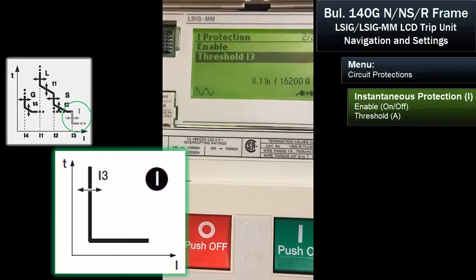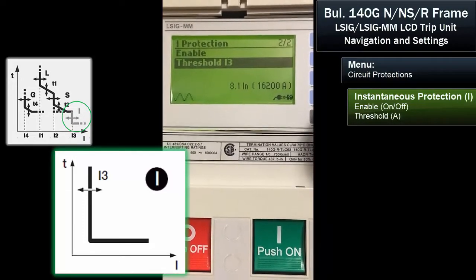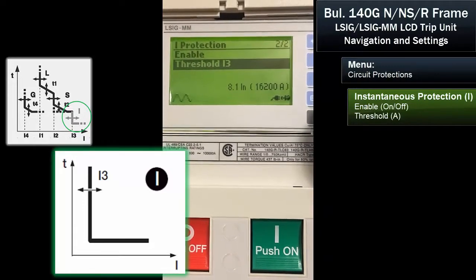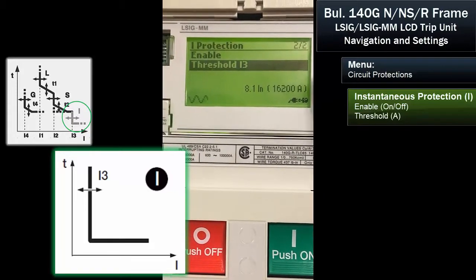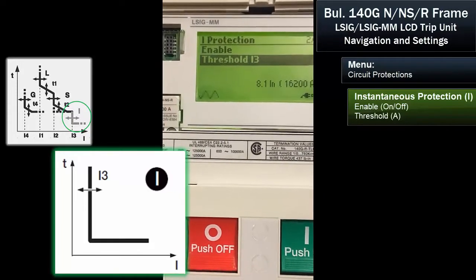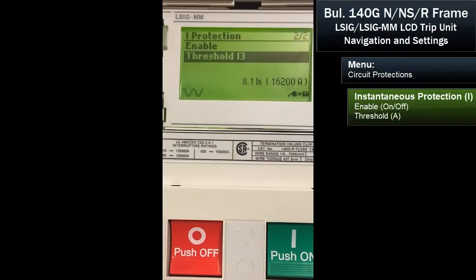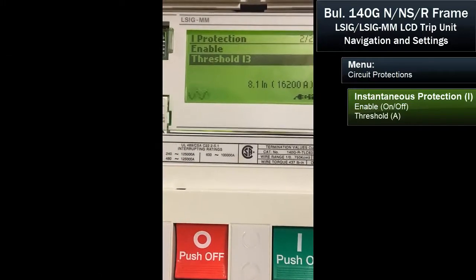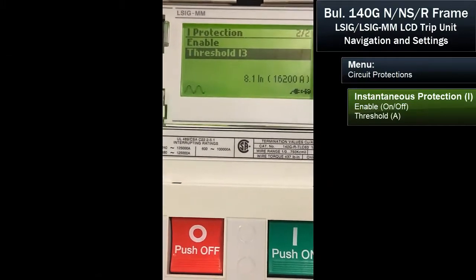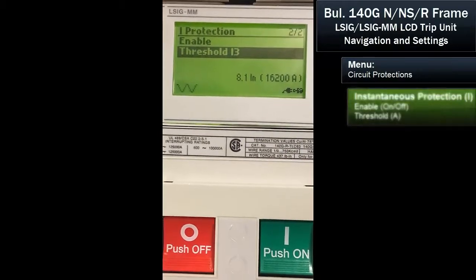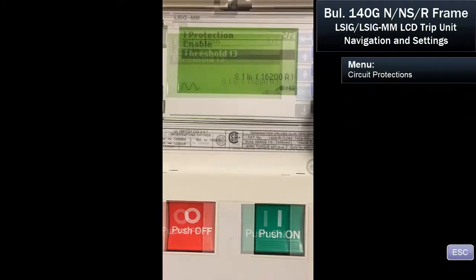Notice that we don't have a time delay — it's exactly what it says: instantaneous. It'll trip once the current reaches 16,000 amps, or 16,200 amps because it's 8.1 times the rating of the breaker.